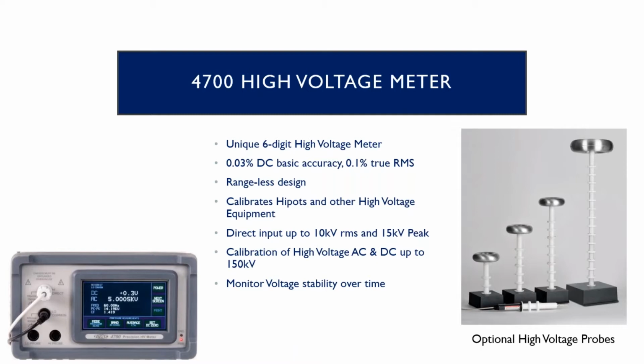People typically use this for calibrating hipots, but also any other high voltage equipment, so a lot of Cal labs use this for calibrating all of their hipots and high voltage equipment. We can take a direct input up to 10 kV RMS and 15 kV peak, just with banana jacks. When you go above that, we have the high voltage probes, for calibration of probes up to 150 kV, RMS or peak—we don't really care which. One of the things the meter does is monitor voltage stability over time.